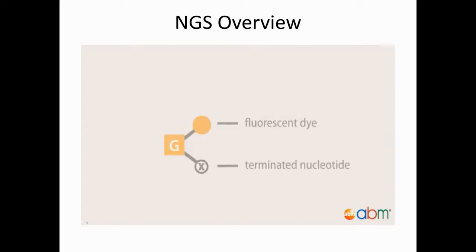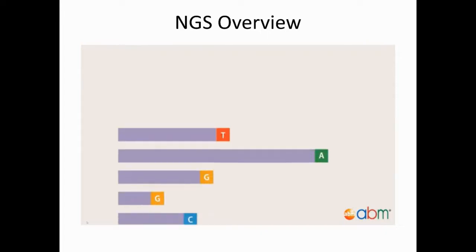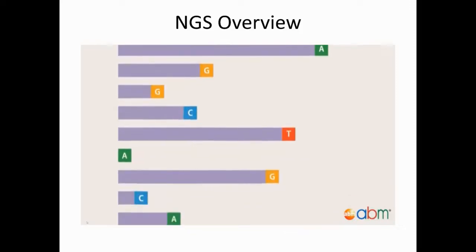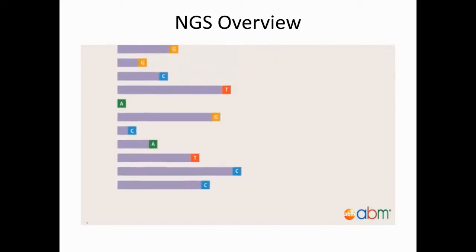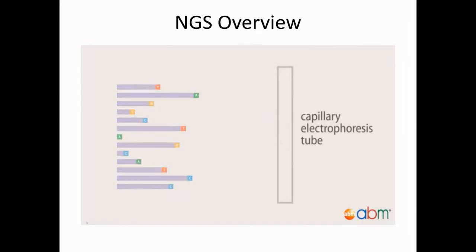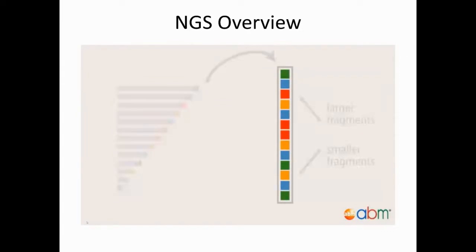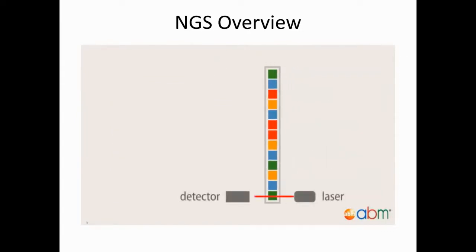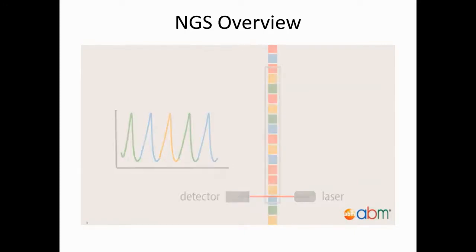As a result, many copies of different length DNA fragments are generated in each reaction, terminated at all of the nucleotide positions of the template molecule by one of the dideoxynucleotides. The reaction mixtures are loaded on the sequencing machine, either manually onto slab gels or automatically with capillaries, and are electrophoresed to separate the DNA molecules by size. The DNA sequence is read through the fluorescent emission of the dideoxynucleotide as it flows through the gel. Modern-day Sanger sequencing instruments use capillary-based automated electrophoresis, which typically analyzes 8 to 96 sequencing reactions simultaneously.